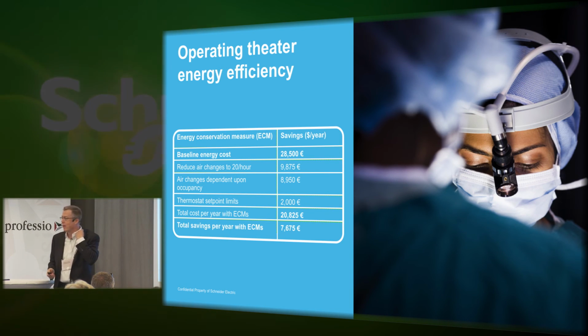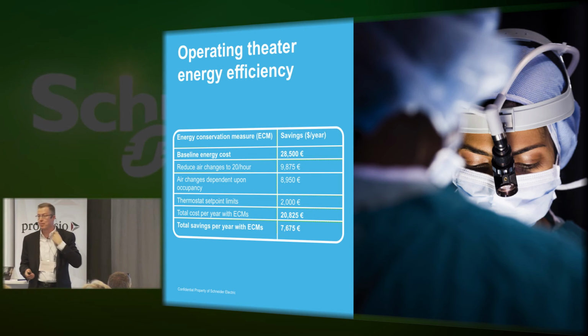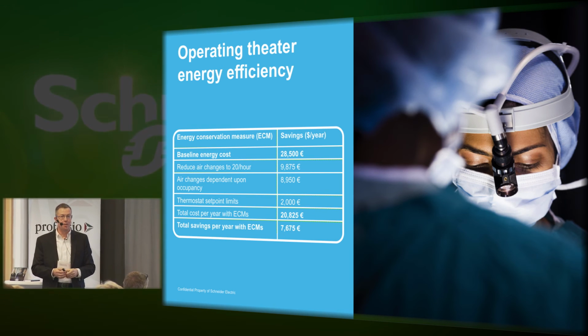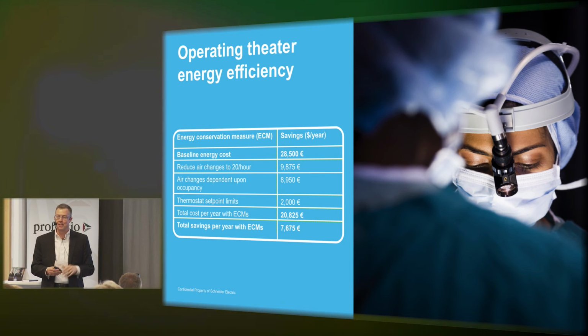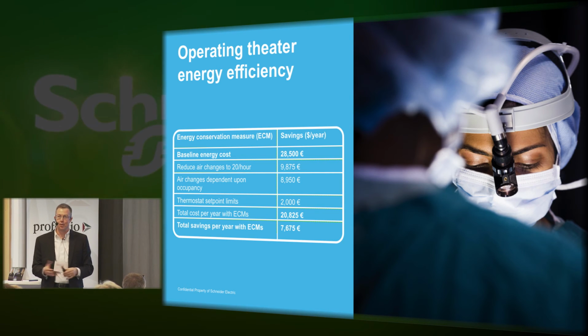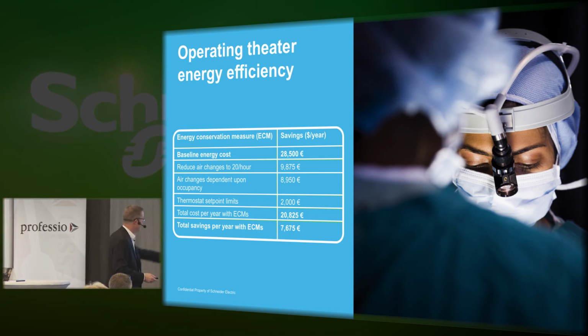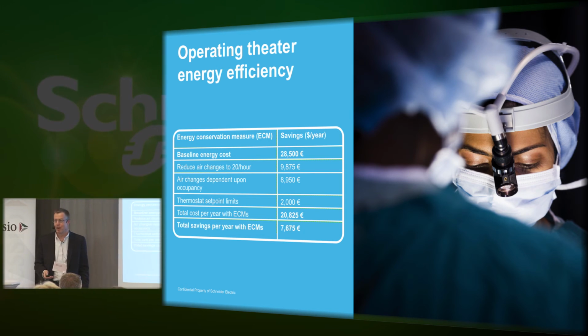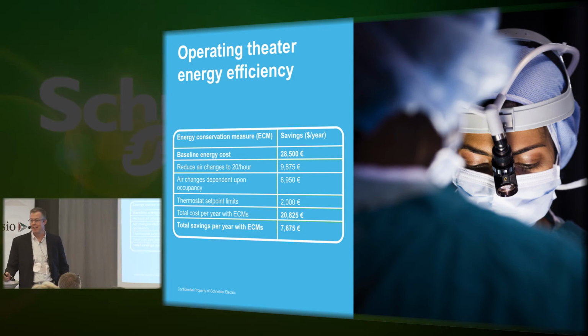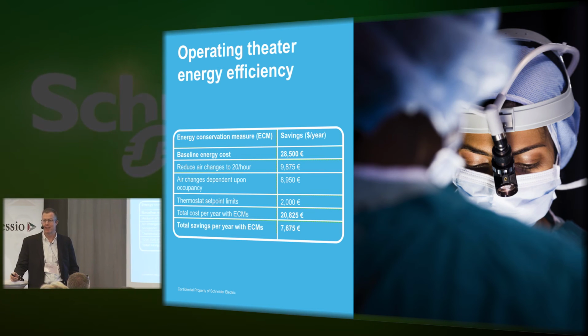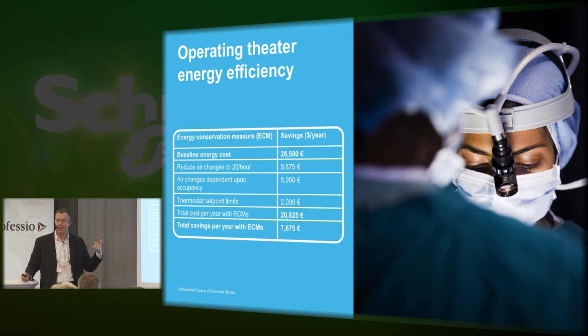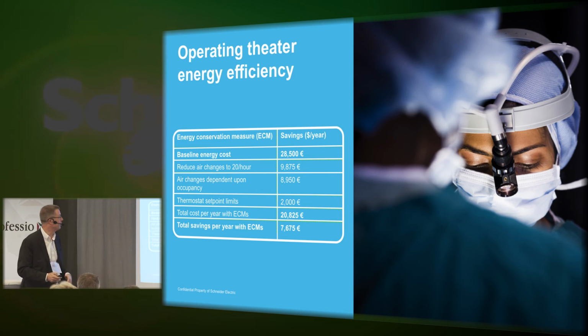You leave one or two running all the time for emergencies, depending on the hospital's strategy, but the rest can be set back to 6 air changes an hour—patient rooms can go to 2. The operating theater can be set to 6 and ramped quickly back up to 30 as capacity demands, saving 7,500 euros per operating theater, times 10, which is otherwise pure waste. That's cost savings, but also hitting green targets and building a greener hospital.